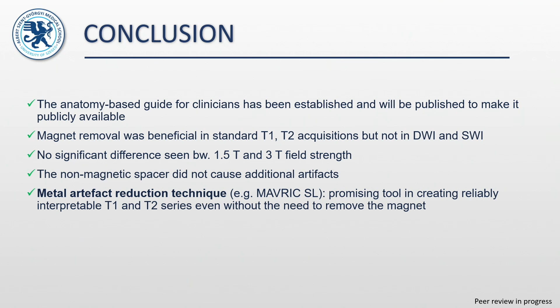We will publish them. We saw that the magnet removal was beneficial in most of the sequences. There was no significant difference between the 1.5 and the 3 Tesla scanners in the results. The non-magnetic spacer did not cause any additional artifact. And importantly, the metal artifact reduction technique, that's what we recommend to use, is a very promising tool to create T1 and T2 series even without the need to remove the implant magnet, which we don't necessarily want to remove.